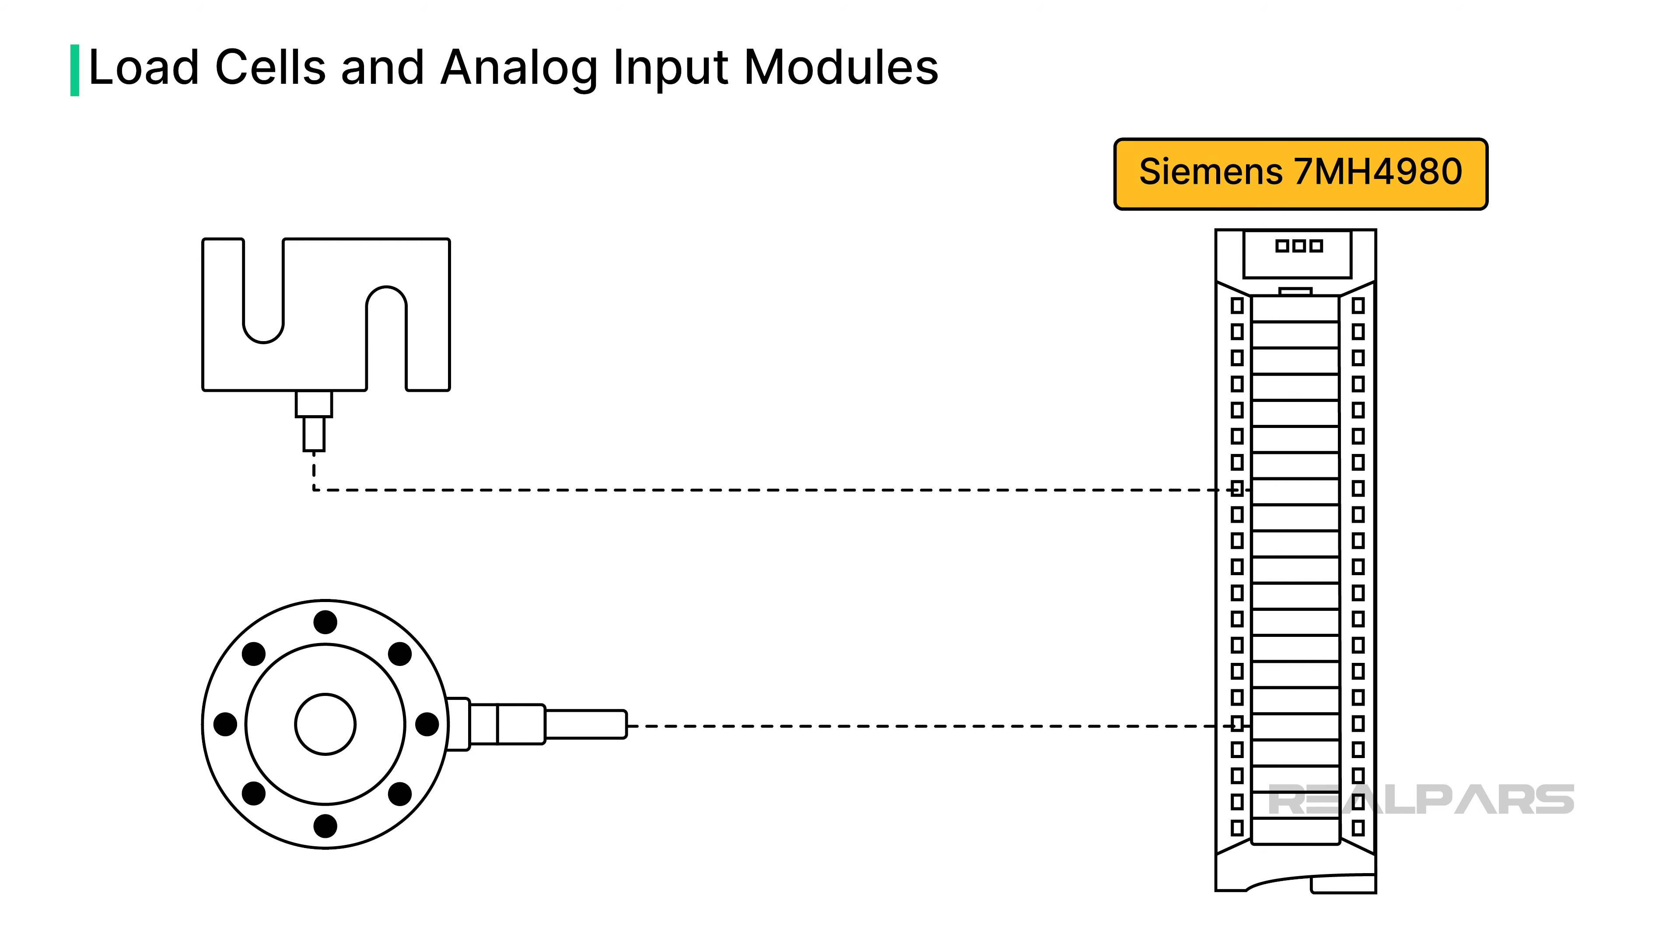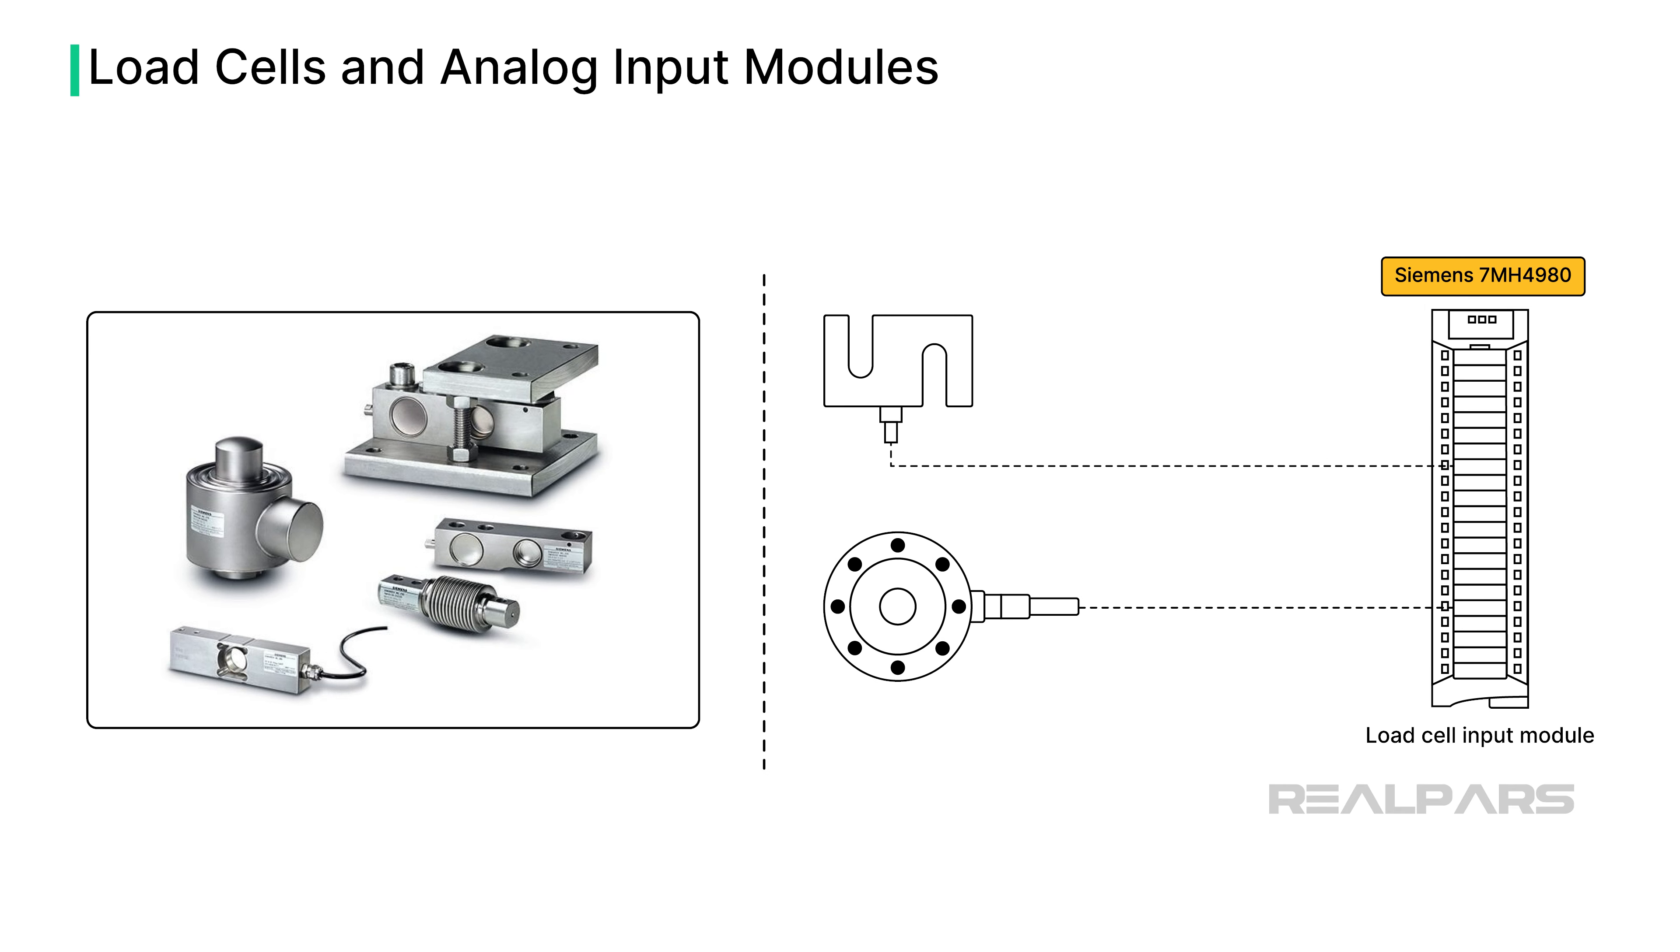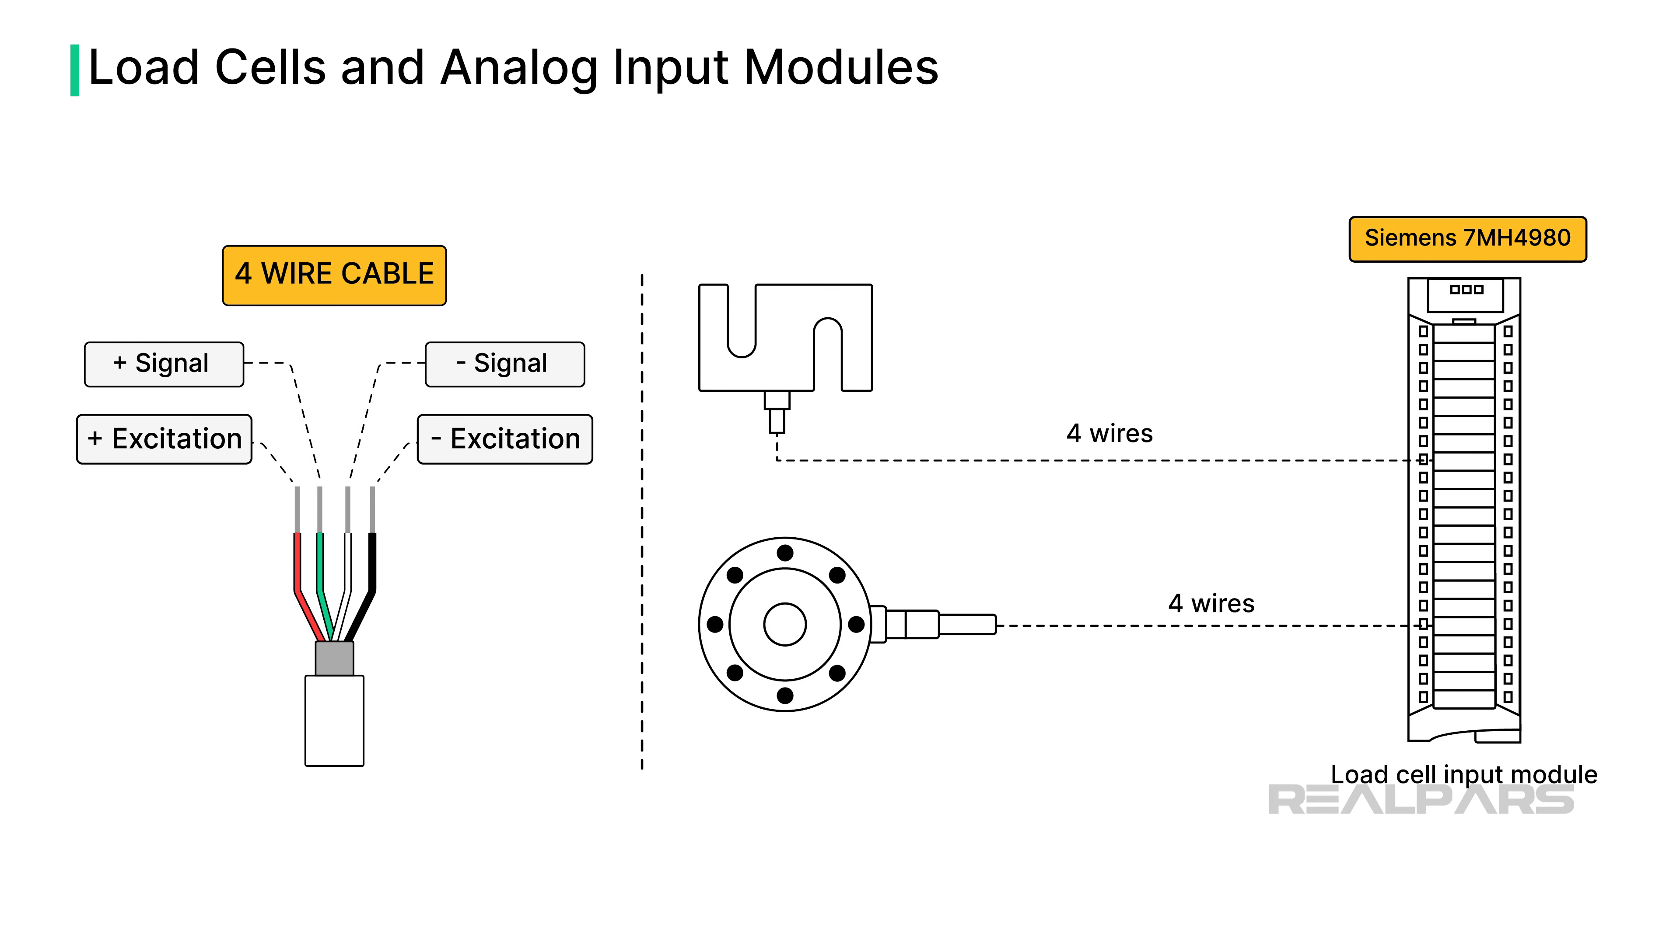Let's discuss the Siemens 7MH4980, an analog input module connecting directly to a load cell. This type of module is often called a Load Cell Input Module. Load cells come in different shapes and sizes, depending upon their application, but they all have at least four wires. Two wires are for excitation, and two are for the resulting signal.